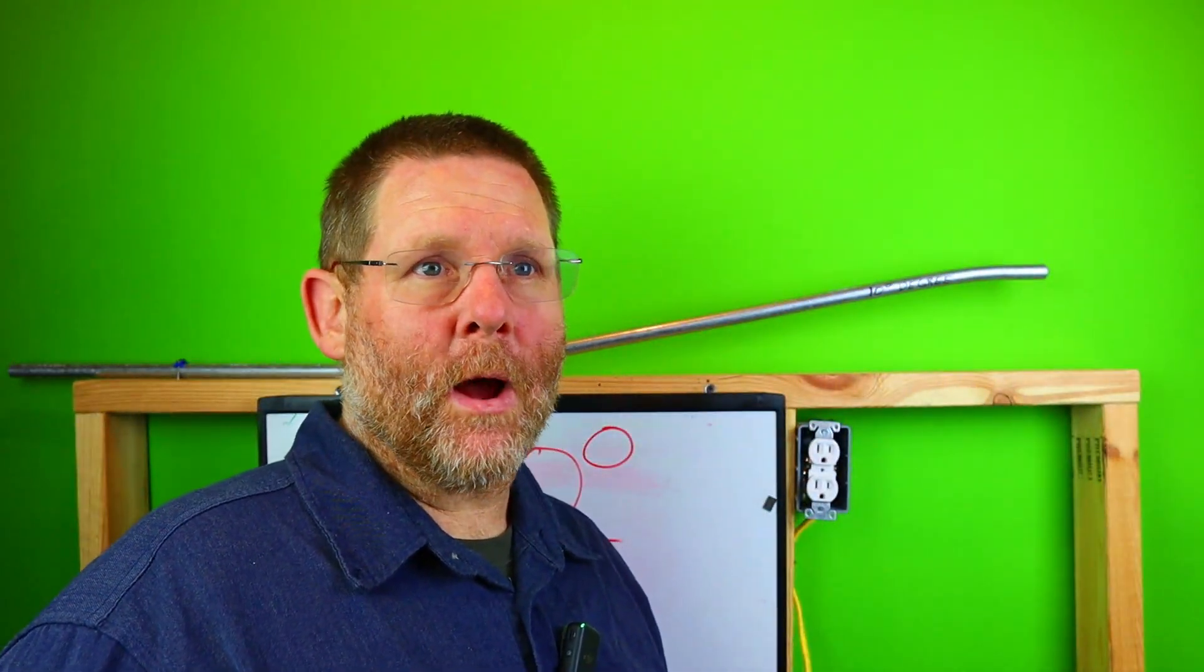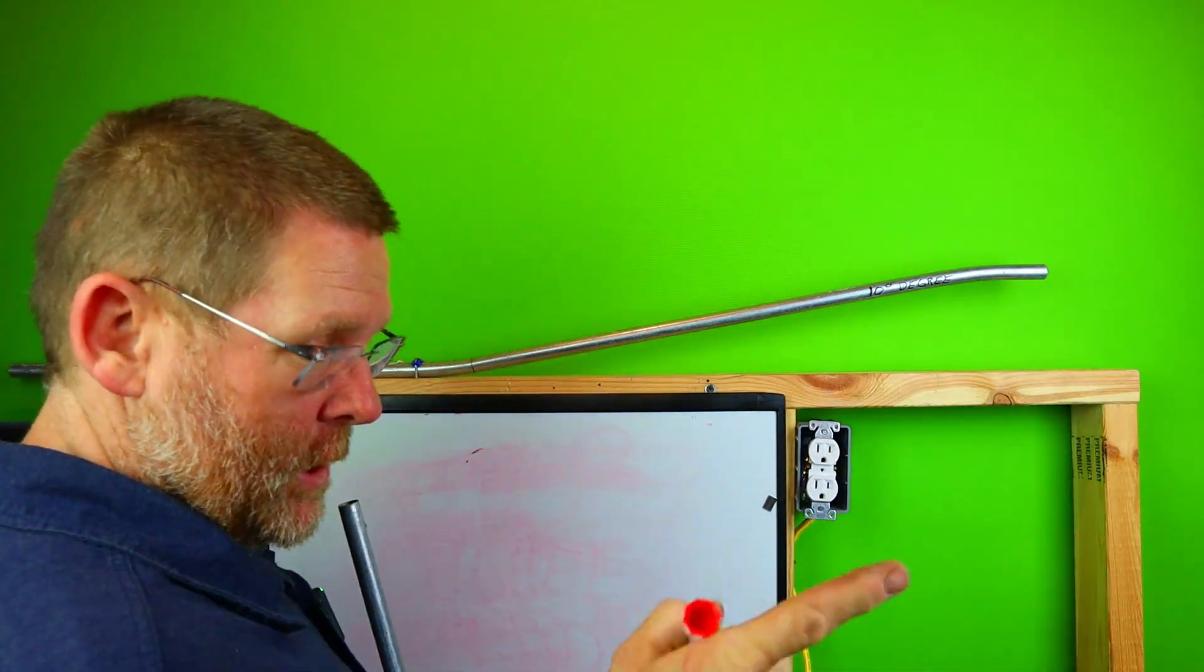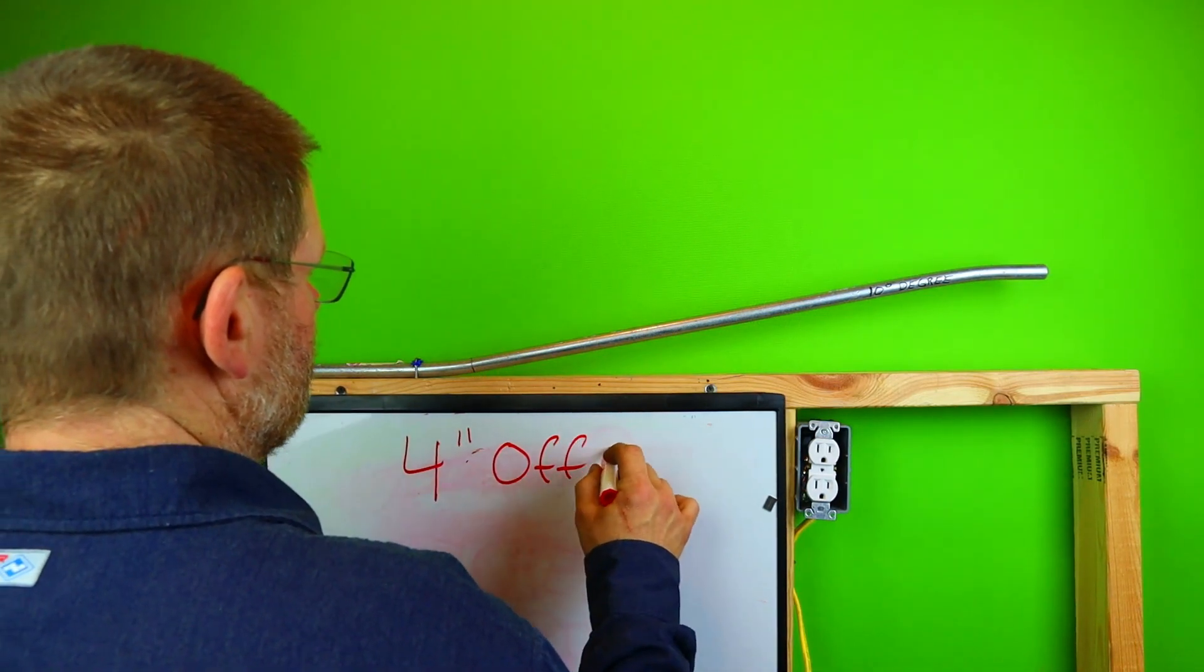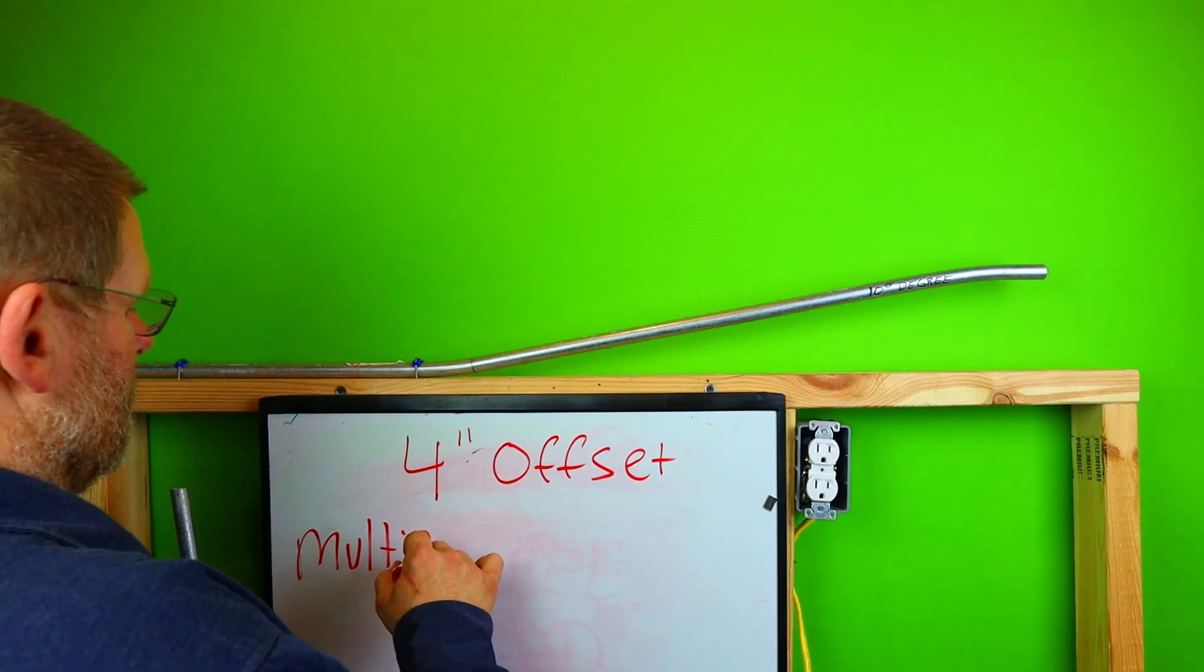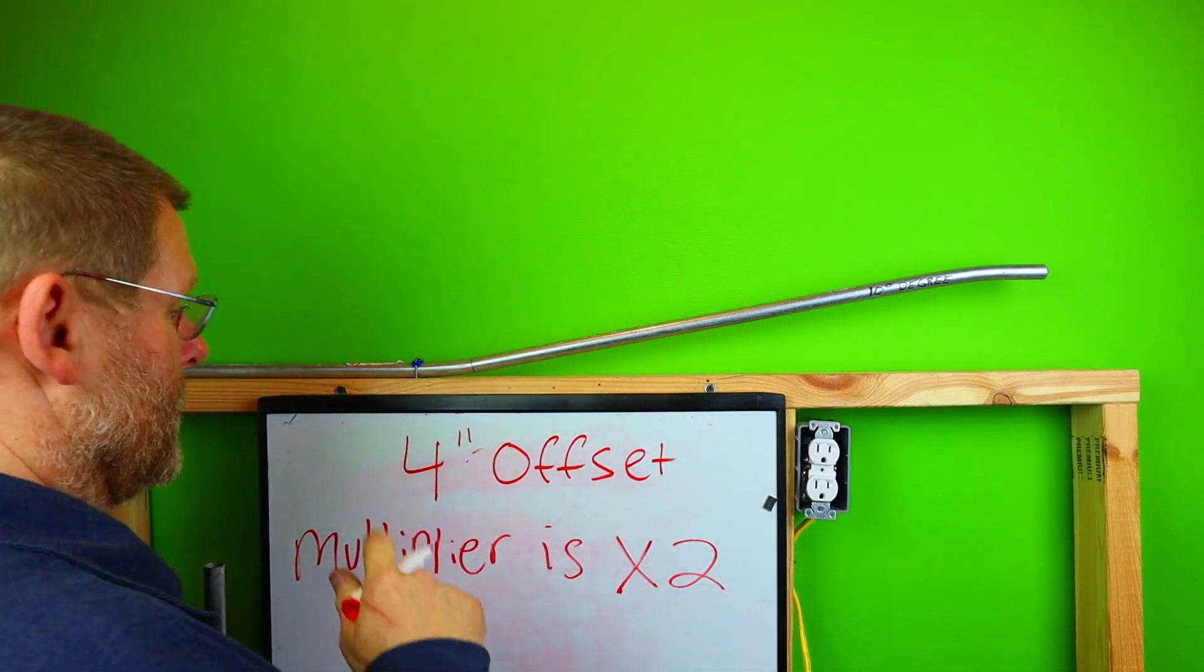Today we're talking about the 30-degree bend, the most widely used bend in all of electrical. It's the easiest one to remember. We're bending a 4-inch offset. How do we do the 4-inch offset 30-degree bend? Let's talk about it. What does the cosine chart say? 4-inch offset multiplier is times 2.